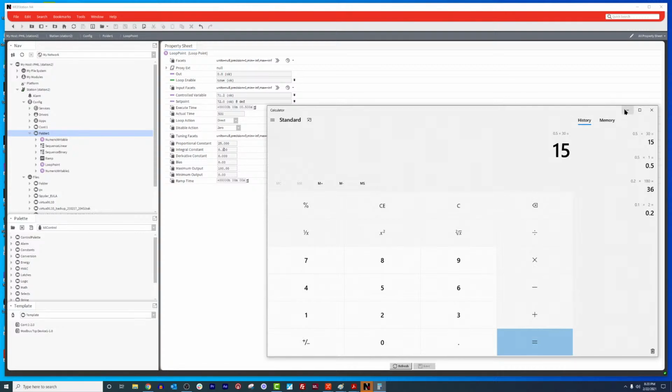Our proportional bands for PID loops on pressure loops are normally like 50 to 60. So 50 plus 15, that's 65 with just a partial load. That's like a partial half of a load on your PID loop, and you're already at 65% output. So that's pretty fast. My general rule of thumb is 0.5 to 1 for fast loops and 0.1 to 0.2 for slow loops.